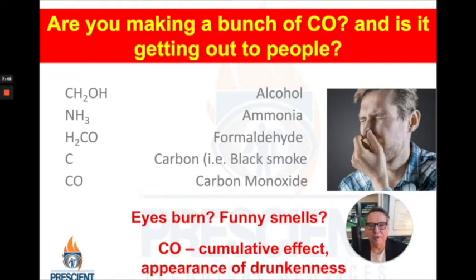If we do get carbon monoxide into the breathing space, it's odorless and tasteless. People may react to a funny smell, but that smell comes from some of these other compounds. You have to be aware that if people are complaining of red eyes, sinus reactions, fogging glasses, or moisture dripping from windows, all of those are indicators that we could be backdrafting and putting materials from the flue products into the space — materials that are not very healthy and probably contain a lot of CO.